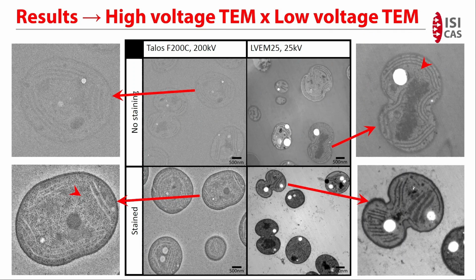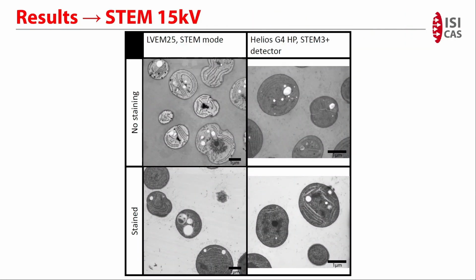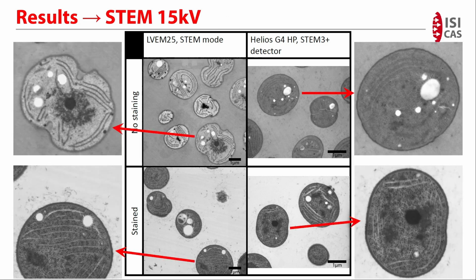Nevertheless, the unstained samples imaged by the 25 kV beam gave us sufficient contrast, quite comparable with stained samples imaged by the high-voltage transmission electron microscope. Unfortunately, stained samples imaged at 25 kV were in some cases, on the contrary, too dark to recognize all of the structures in the cells. Also, it is possible to see that both images acquired by LVEM25 are not as sharp as the high-voltage image because of the chromatic aberration occurring when imaging thicker samples with low-energy electrons. This issue, however, can be overcome by switching to STEM mode. As you can see, both of the images acquired by LVEM25 are sharp and provide nice contrast.